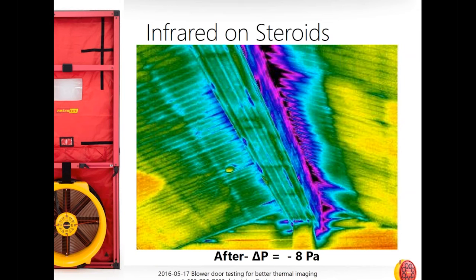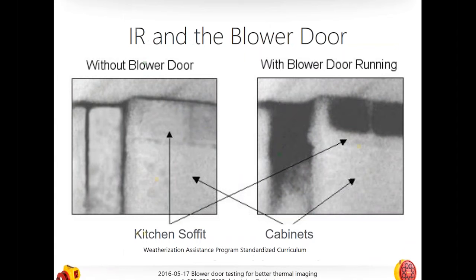When temperature is similar between inside and outside, just using a little bit of blower door can make a big difference. And even when there's quite a bit of temperature difference, it's really important to use the blower door with the infrared camera because it gives us images on steroids — it immediately makes a big impact and accentuates the differences in the thermographic pictures.